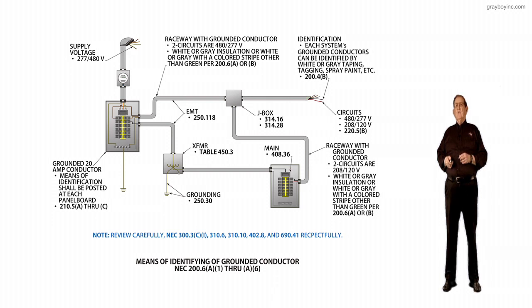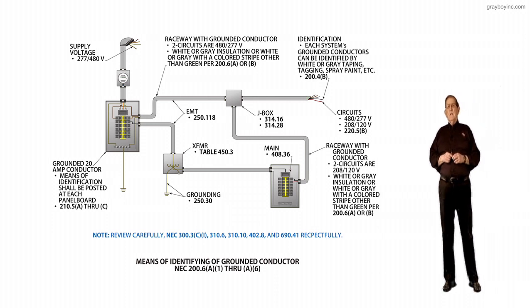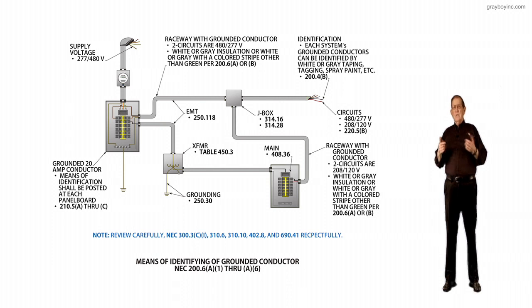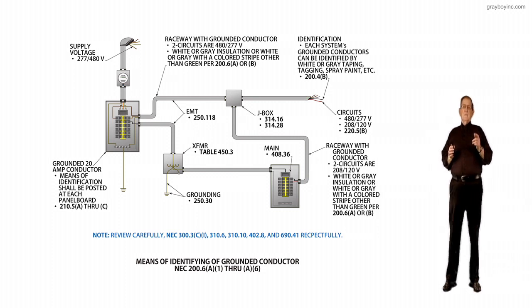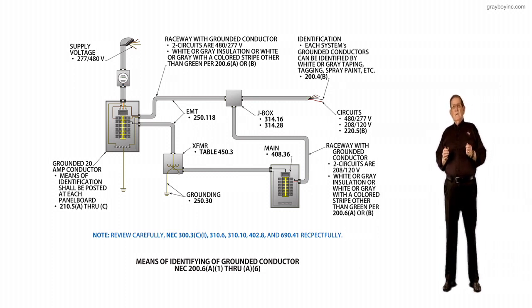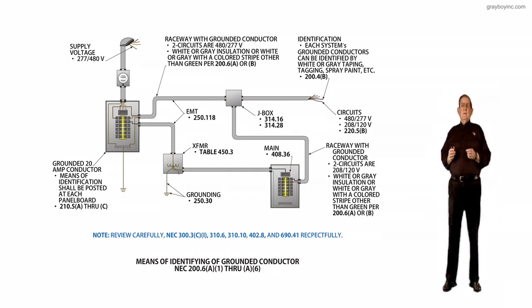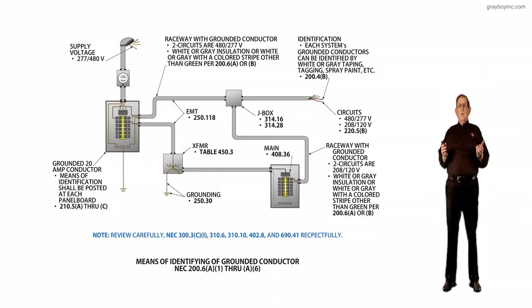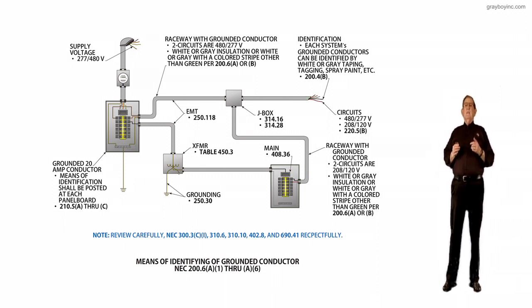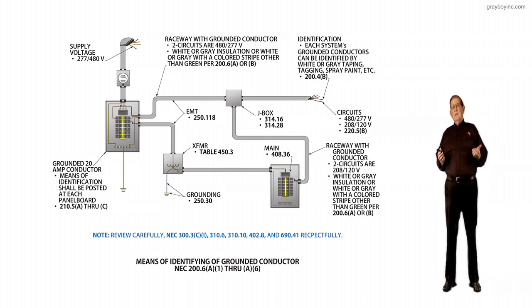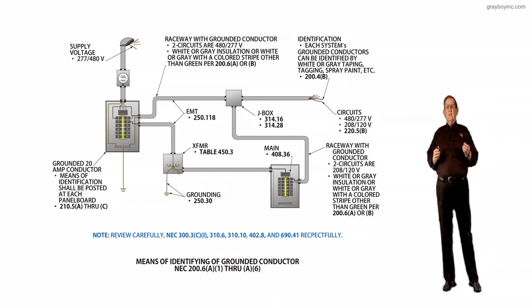NEC 300.3C1. Now that's where we can mix 1,000 volt or less conductors in the same raceway, junction box, etc. 310.6 now deals with references to say 200.6 for the grounded conductor, 250.119 for the equipment ground, 210.5B or 210.12C for the grounded conductor. 215.12C deals with the feeder conductors and how you would identify the ungrounded conductors. So you want to review very carefully 310.6, A, B, and C.